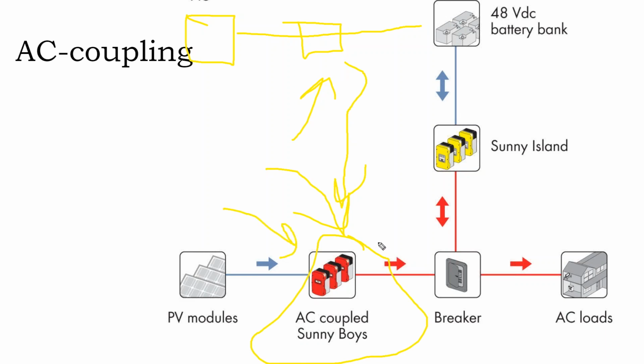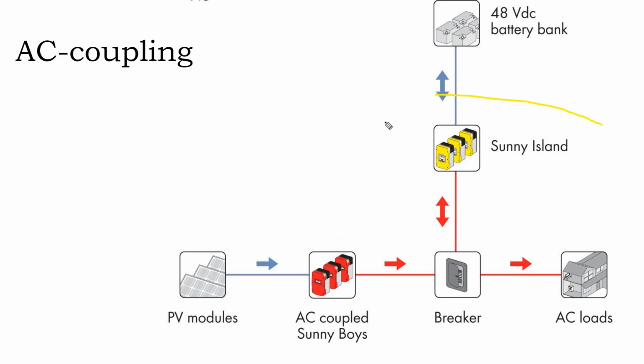That dedicated inverter is going to add to the power output capacity of the battery system, at least during the day. So, all else being equal, an AC coupled system is going to give you more ability to power the whole house in the middle of the day with your entire system. That could be the difference between an off-grid system that doesn't run your air conditioning at all during an emergency versus one that runs the air conditioner during the day and then turns it off at night to let the batteries and inverter serve other more critical needs.